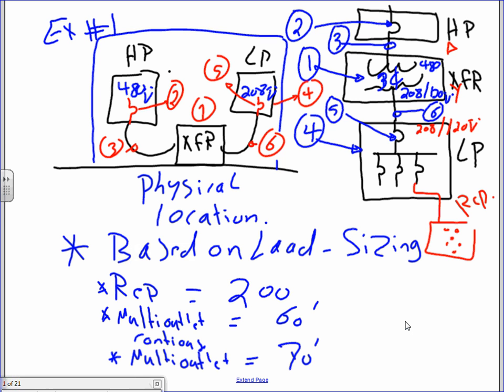And you guys remember we put 6 receptacles in a commercial building on 20 amp circuits, right? 6 to 8. So this will be 6 to 8 receptacles fed from that 20 amp branch circuit. Can you see that? That 20 amp branch circuit? And that, let's just say 6 receptacles. Okay, does everybody understand what we have here?